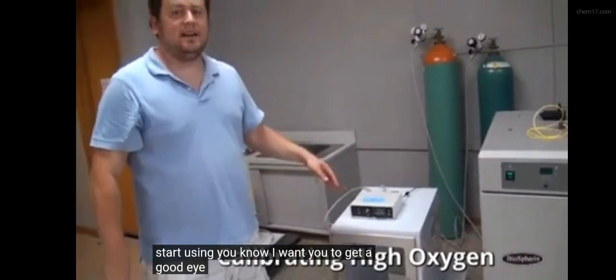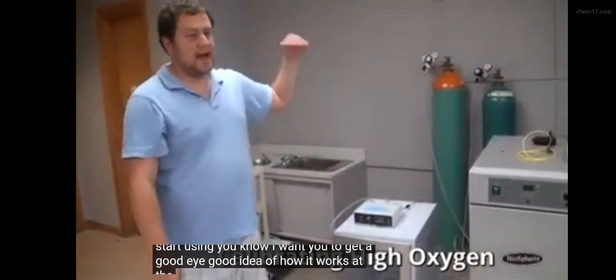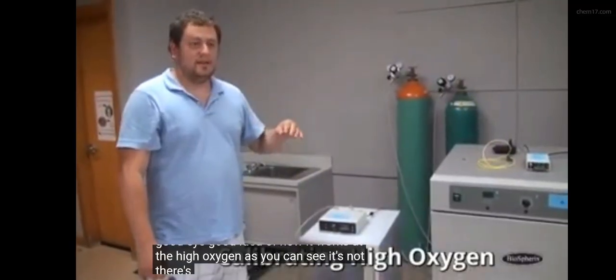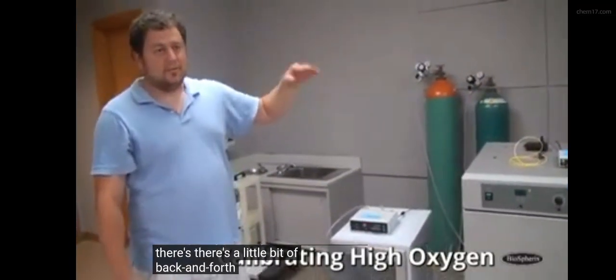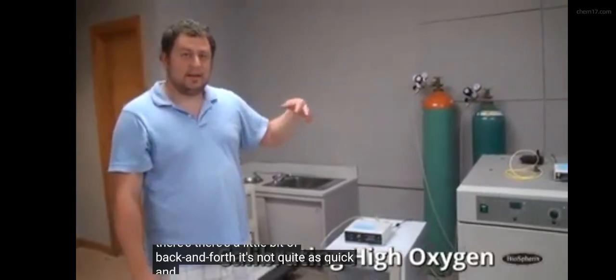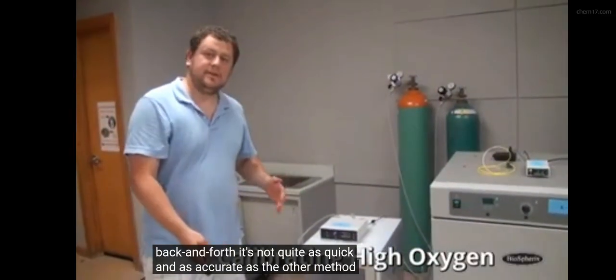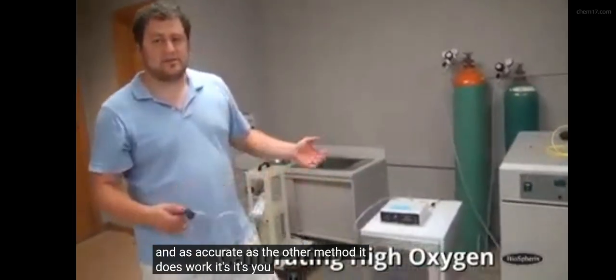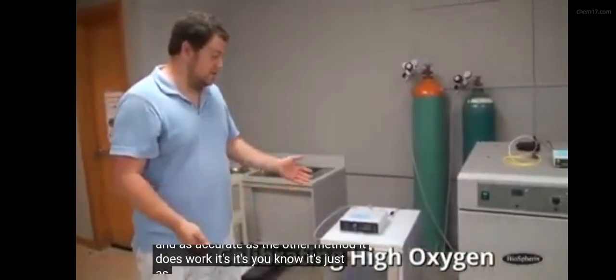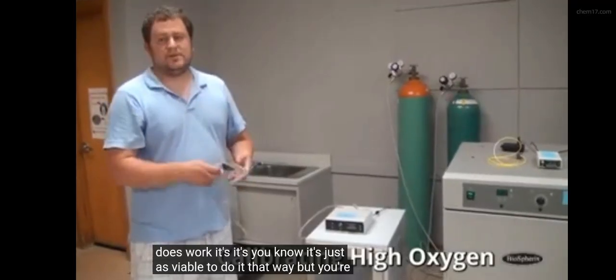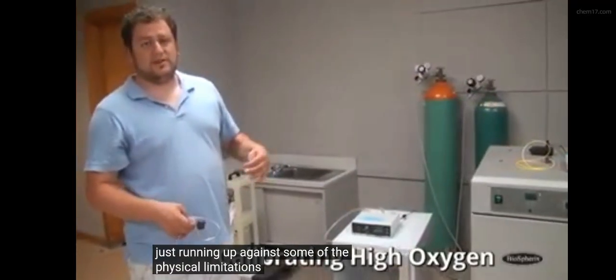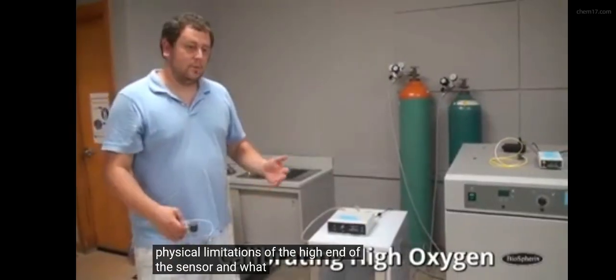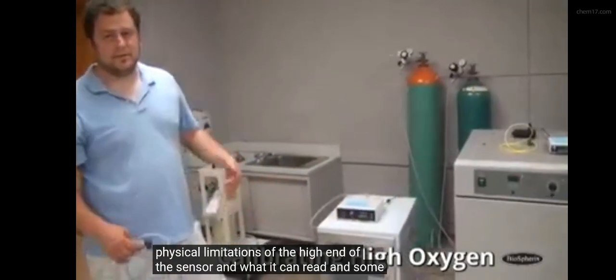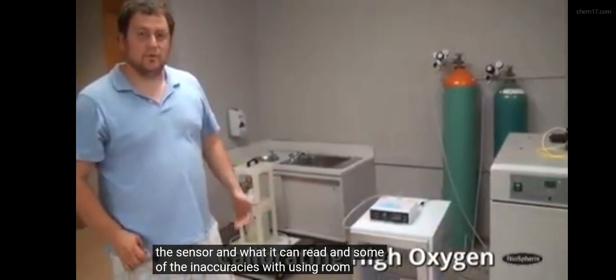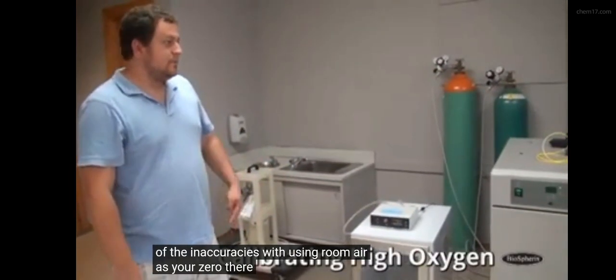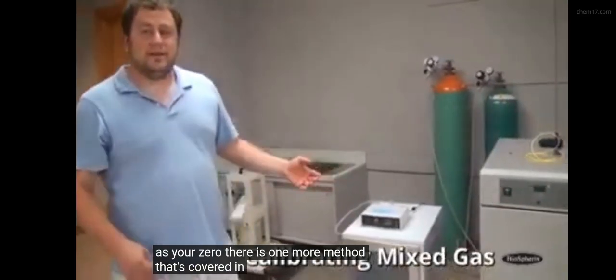I want you to get a good idea of how it works at the high oxygen. As you can see, there's a little bit of back and forth. It's not quite as quick and as accurate as the other method. It does work. It's just as viable to do it that way, but you're just running up against some of the physical limitations of the high end of the sensor and what it can read, and some of the inaccuracies with using room air as your zero. There is one more method that's covered in the manual.